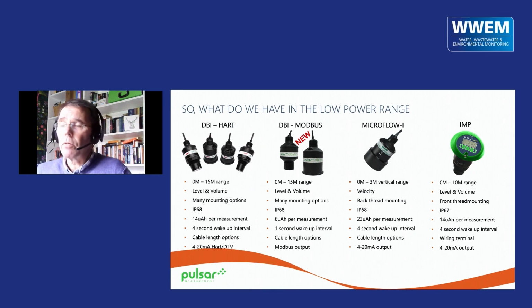This is the range of our low power sensors, and they all use this very quick boot up time. The IMP on the right hand side was our very first iteration, quickly surpassed by the dBi, because we found that even the IMP, in sewer applications, if it got surcharged, there could possibly be a leakage issue if the cables hadn't been tightened through the cable glands, that type of thing. So the dBi is fully potted, IP68, and you can see along the line the actual power per measurement.